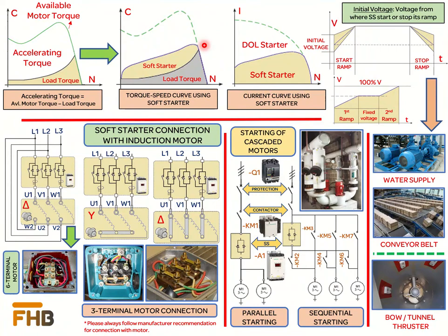Different starting techniques are used in soft starters. The time-voltage ramp technique is based on the fact that by reducing the applied voltage, the starting current will be reduced. However, this also reduces the motor available torque. Therefore, this technique is not suitable for loads which require higher starting torque.